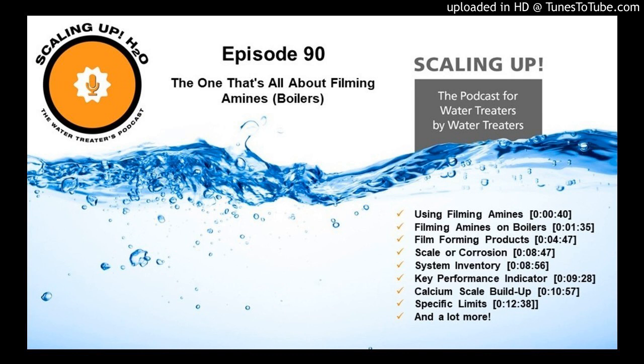Because if we have chemistry loading into a boiler or a makeup tank or a holding tank or a DA, whatever, if application's on that end, it is an all volatile treatment. We're going to go in and we're going to film and maintain pH from the point of application all the way till the point that it returns. Well, if I look for residual and iron and pH, right? That's my little trifecta that I really, really care about. If I look for those items at the furthest point and I have no metal and I have a healthy pH and I have a residual, then I feel comfortable saying that we have filmed all of the surface area up to the point of sampling.